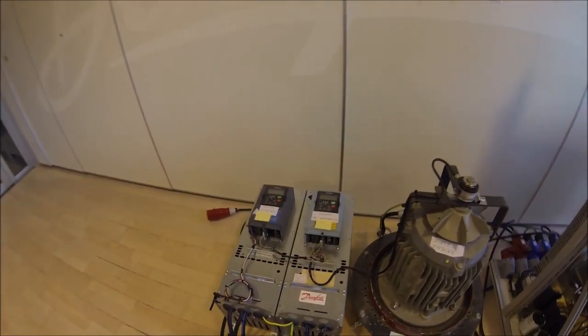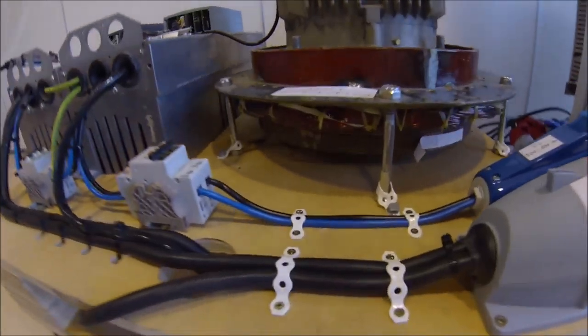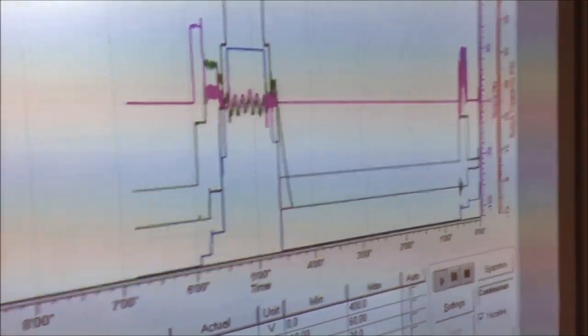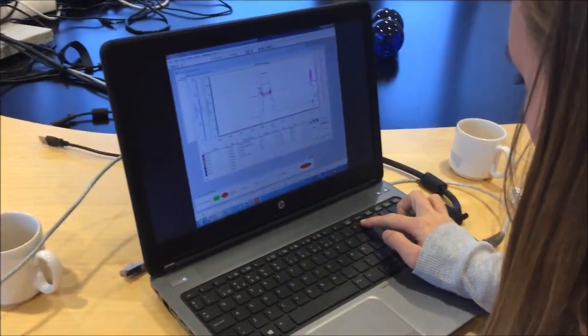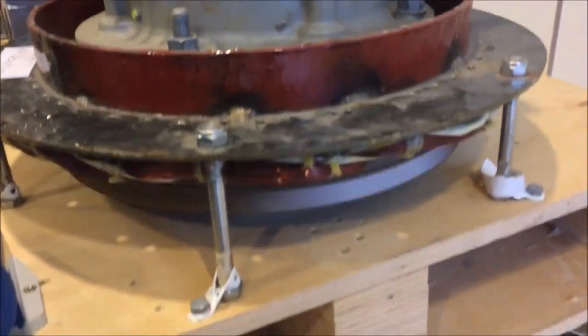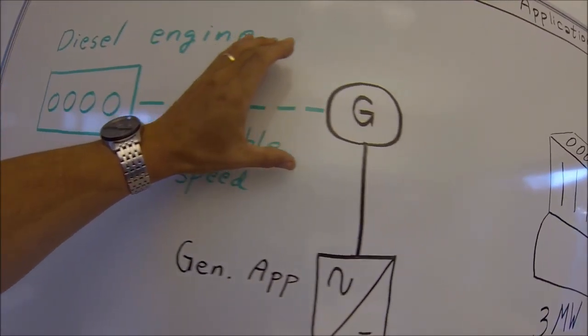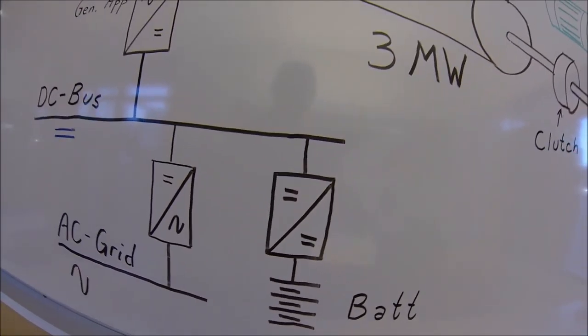Today we are going to look further into the shaft generator. It's a regular frequency converter with special software which in this case handles a permanent magnet motor. Typical usage is between a diesel engine and a generator, which can be a synchronous or asynchronous machine. On the grid side is the DC bus, which can be connected to the AC grid and even to energy storage.